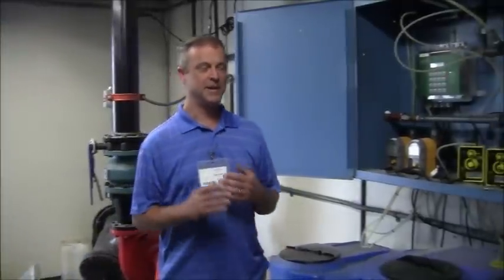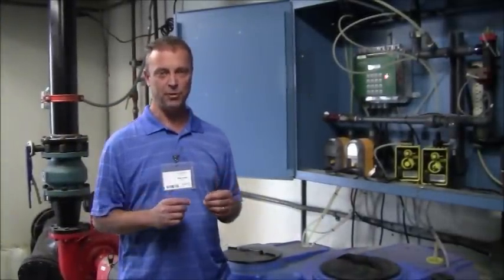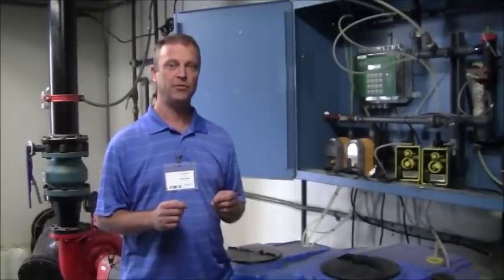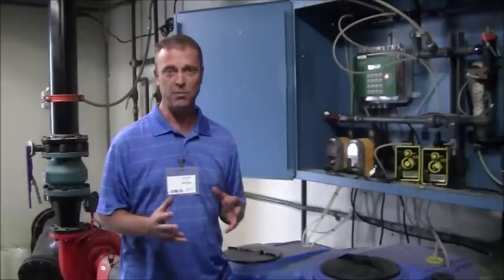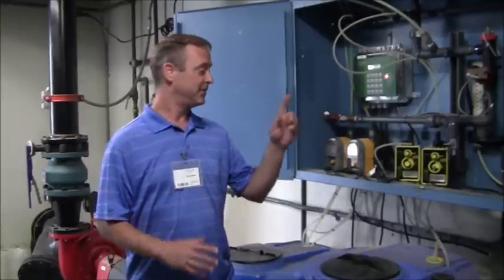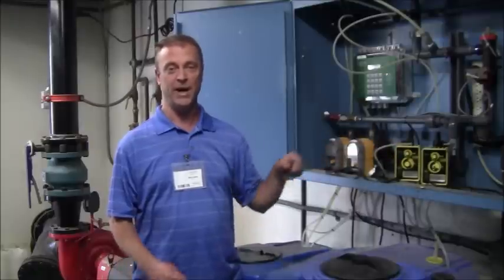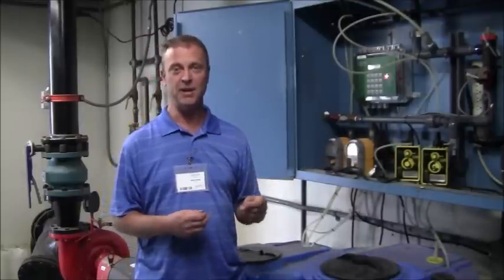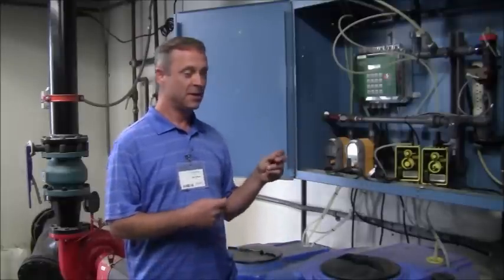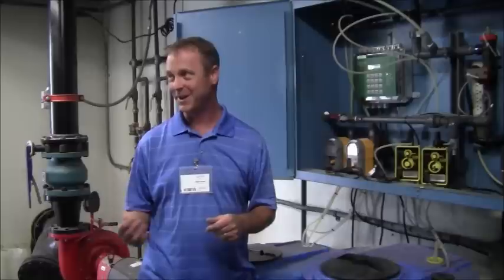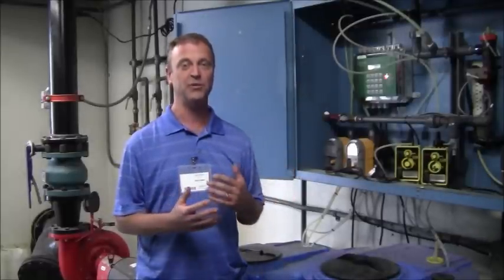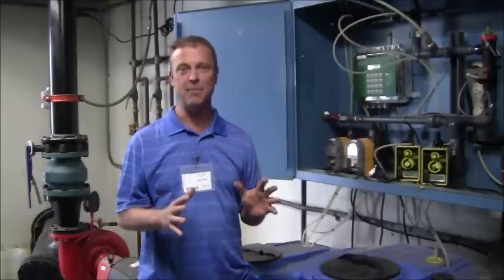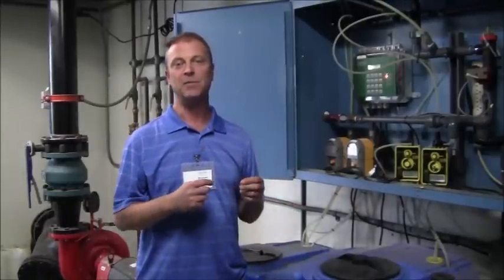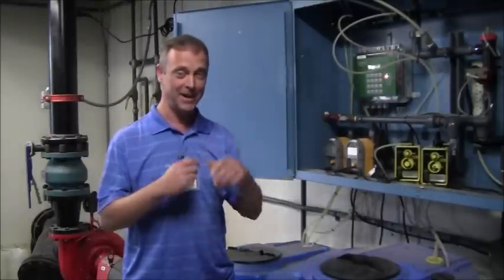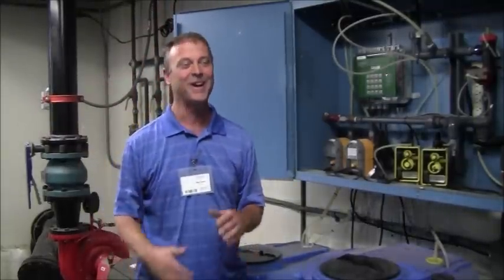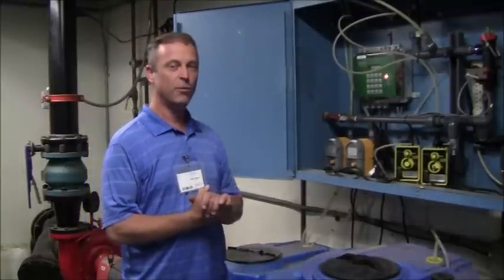That's correct. Ken mentioned a very good point. The absolute number one way anyone gets hurt, especially building engineers and water treatment professionals pouring chemical, is the chemical pump. People don't realize that it's still plugged in, they didn't isolate it, the tubing cracks, the pump starts pumping, the controller calls for something. They didn't take the time. They're busy on the radio or whatever, they stop in the process of working on the chemical pump, and something feeds or something goes off, and you get dinged in the eye, or you raised your face shield because you couldn't see very well. I've seen it all, but it is the number one way people get injured.